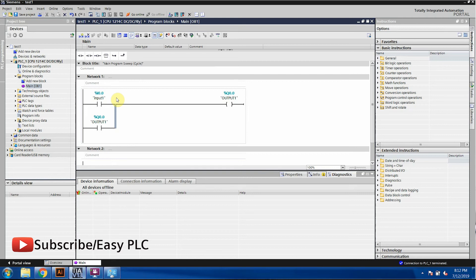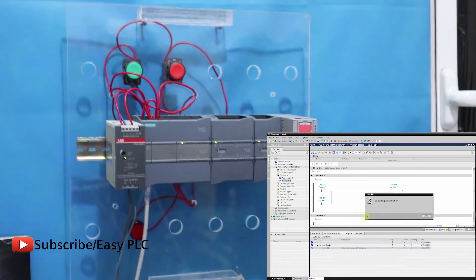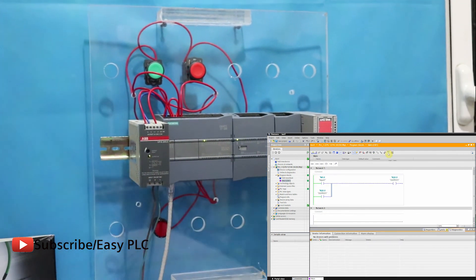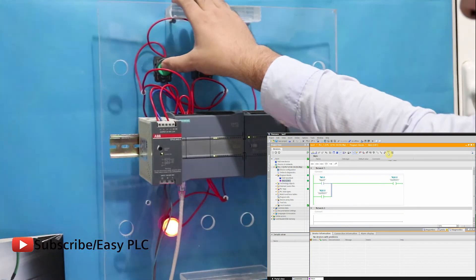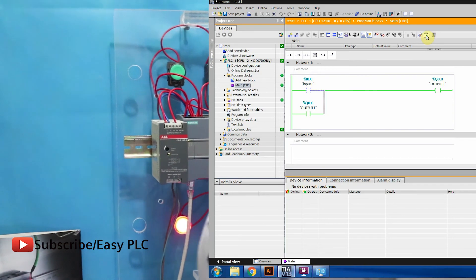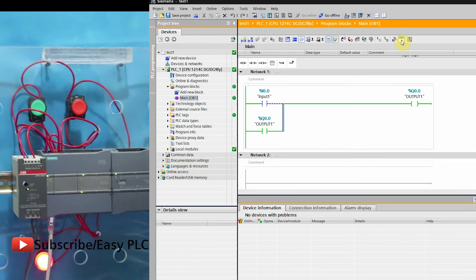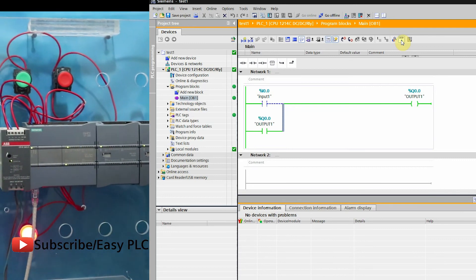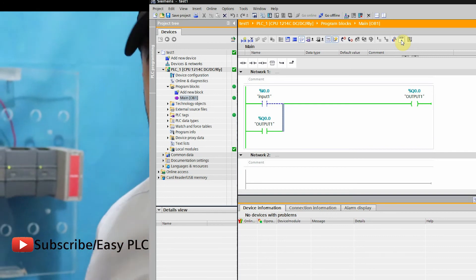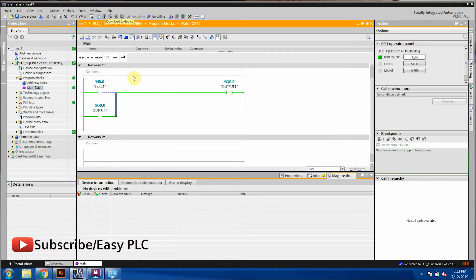First we create the problem, then we will sort it out. Let's go back to hardware simulation. I download the program and take the online view. When I press this button, our output is high. Even when I remove my hand from the push button, the output is still on. But now there is a real issue — how do we turn off this output? We need some other stop button for that.